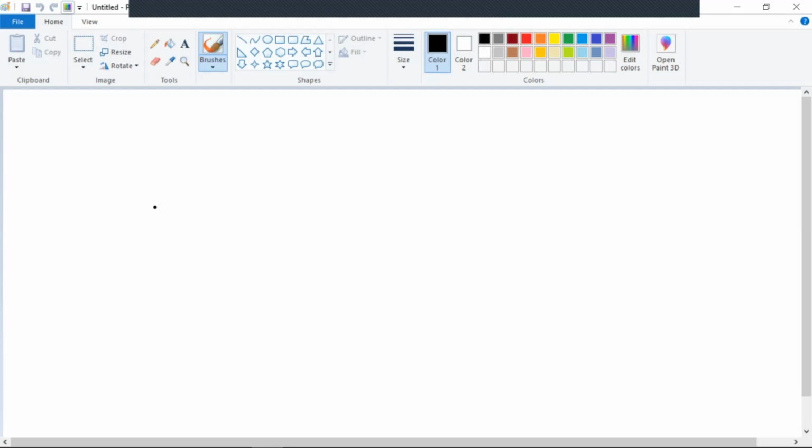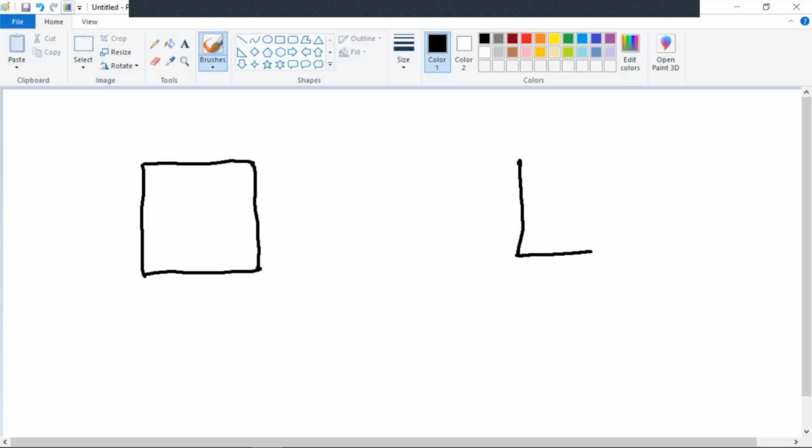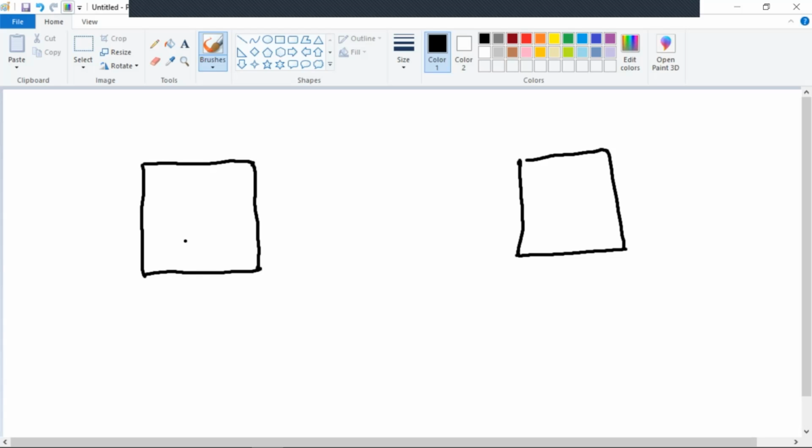And this is something that you need to look out for when you observe inside the transformer. I'm going to put T1 as a square box looking straight down into the ground, and T2. This is where you guys, especially if you're the trouble person reporting this information, or you're the person getting ready to come and repair it, know what you're going to need to have. This is where you look inside the transformer.